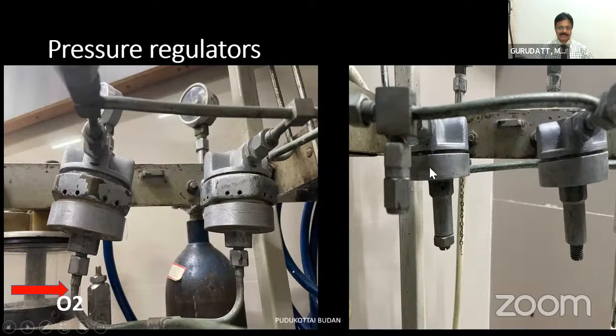So why I am keeping these both is that there is a difference between these pressure regulators of nitrous oxide and oxygen. The nitrous oxide pressure regulator, which I am showing, has got 3 chambers, unlike the oxygen pressure regulator, which has got only 2 chambers. So there is a connection of oxygen also there for the nitrous oxide pressure regulators. Mainly, the nitrous oxide pressure regulator acts as a slave regulator to the oxygen. So oxygen pressure has to be there to open the nitrous oxide flow. That I'll be discussing in detail in the same lecture, slightly later.